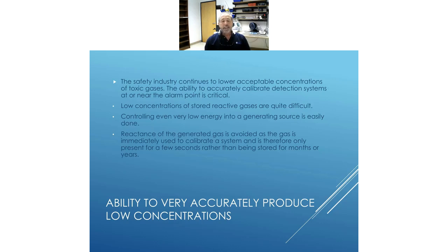This ability to very accurately produce low concentrations is the big deal about these gas generators, because with these very toxic chemicals, you want very low calibration levels to be generated. The safety industry, the governing body in whatever country you live in, keeps lowering the acceptable concentrations. Here in the US, OSHA sets these safety levels and says how many parts per million of whatever gas, as we're talking today, ozone, chlorine, or chlorine dioxide, a worker can be exposed to 8 hours a day, 40 hours a week for 20 years. And typically that's where we alarm a sensor.